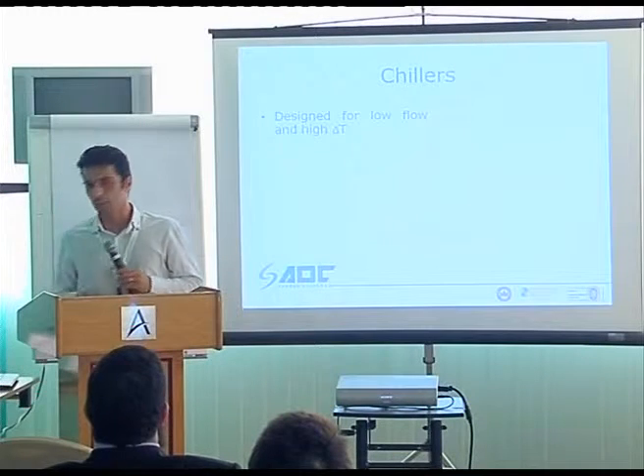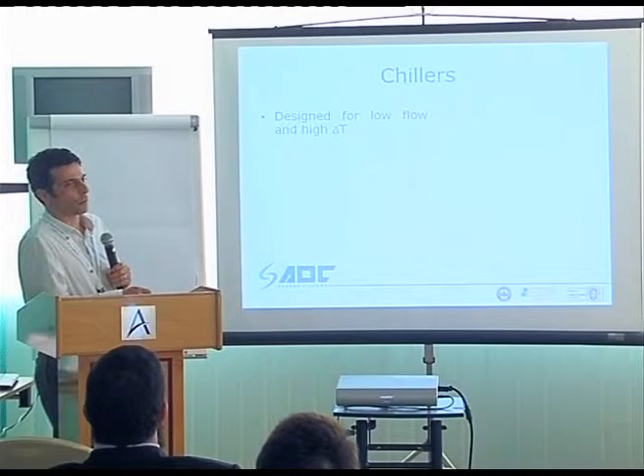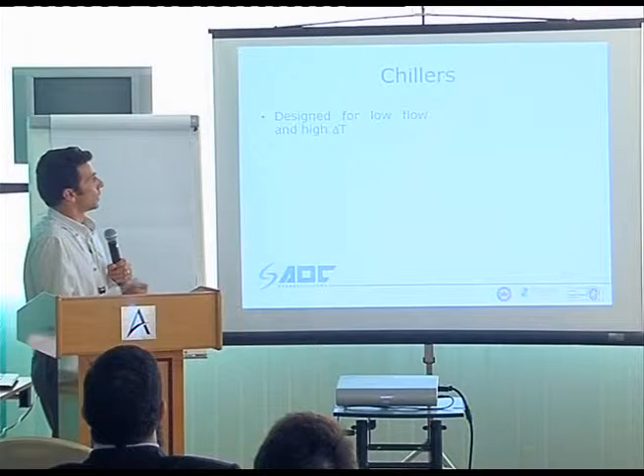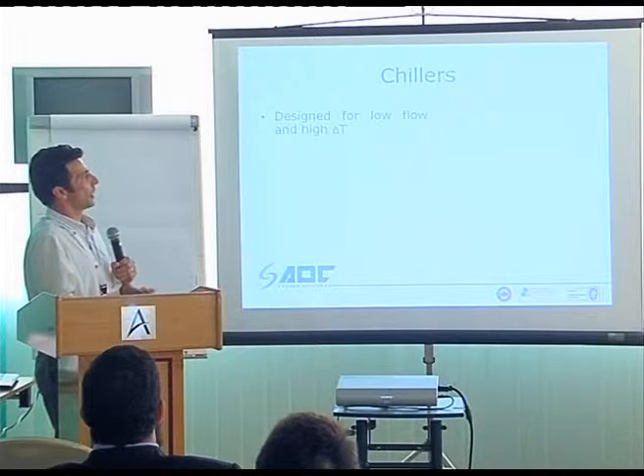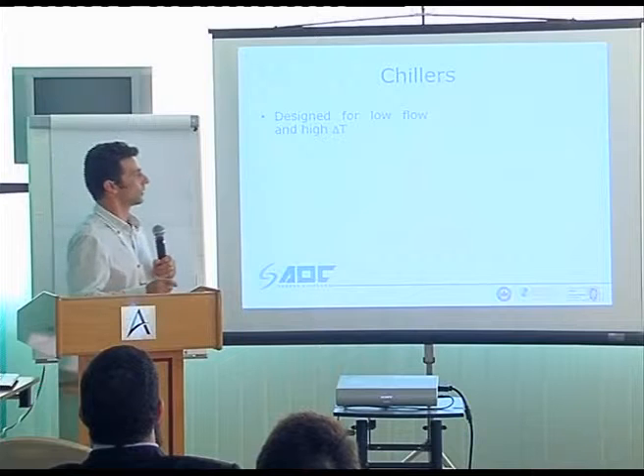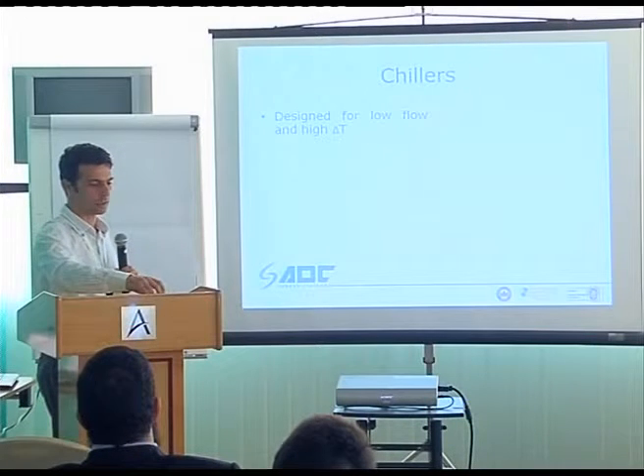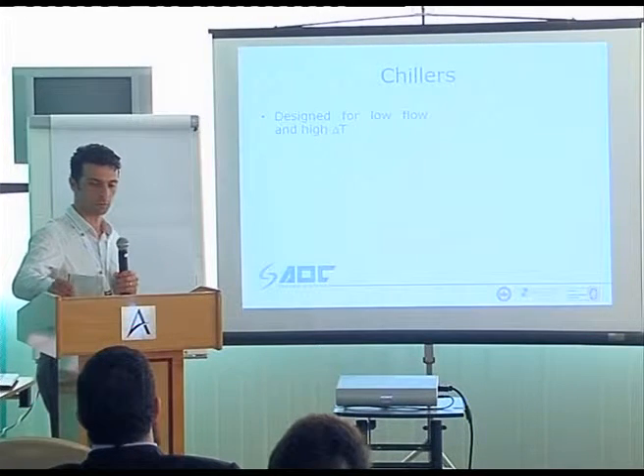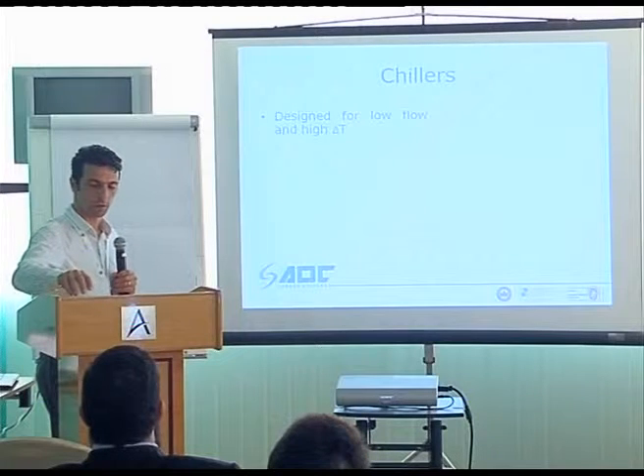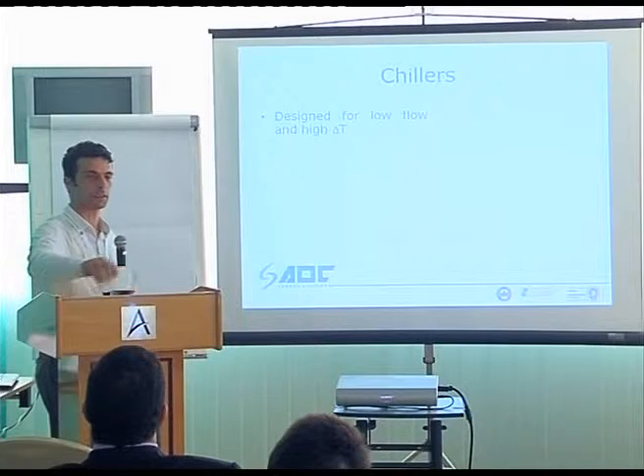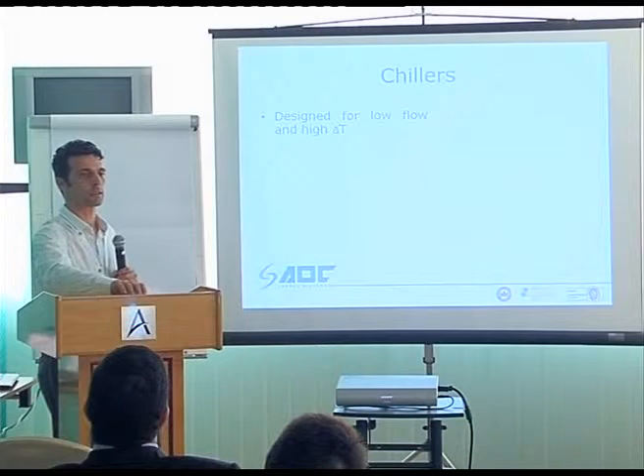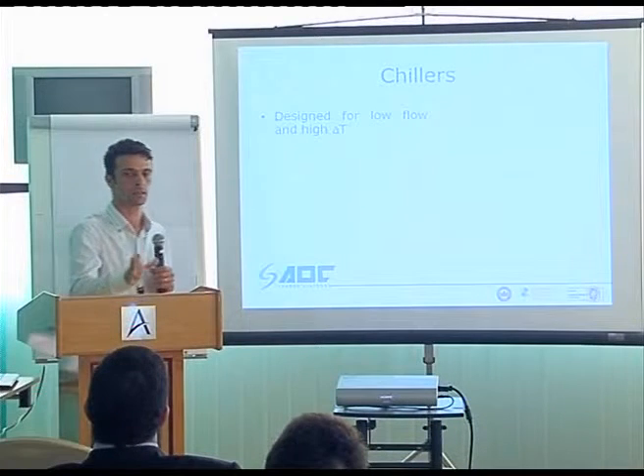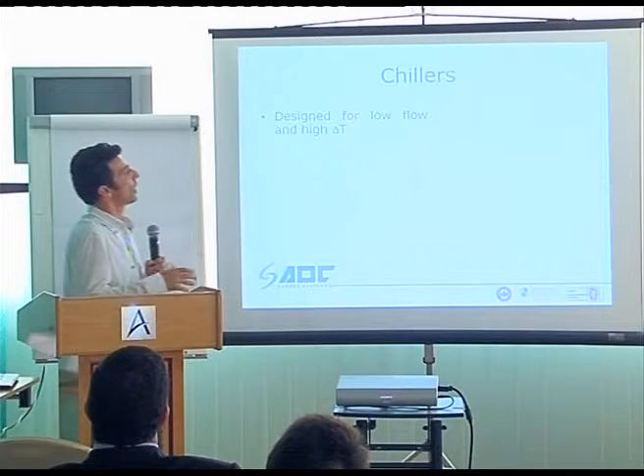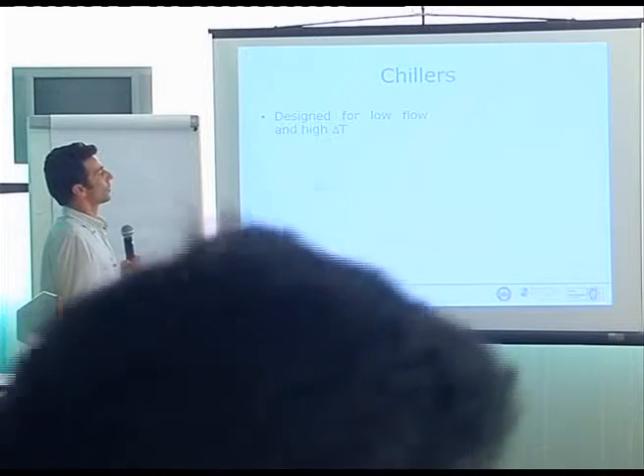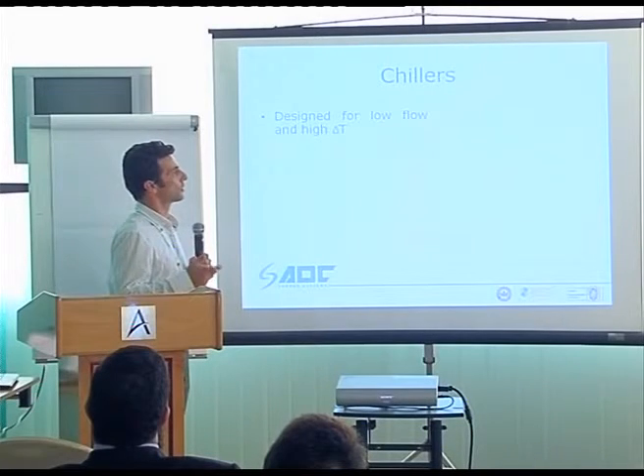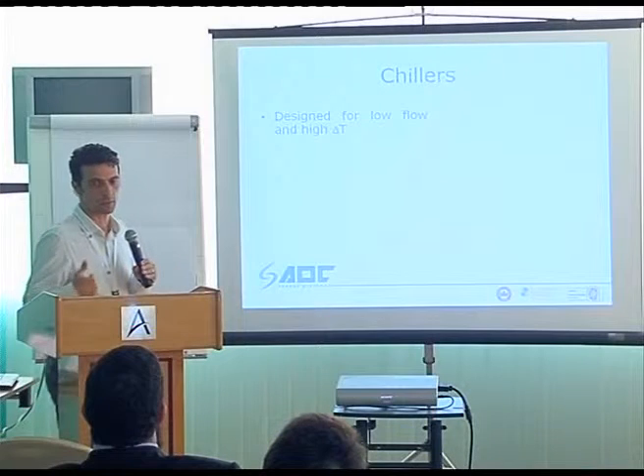The difference, again, I'm going to talk about the chillers and how we select them for a district cooling plant. In the end, a kilowatt is a kilowatt. Whether you produce it in a building or somewhere else, there is a certain kilowatts and a certain load. How do you go about it in district cooling? You minimize your flow and increase your delta T.